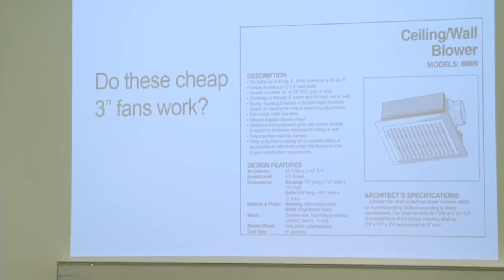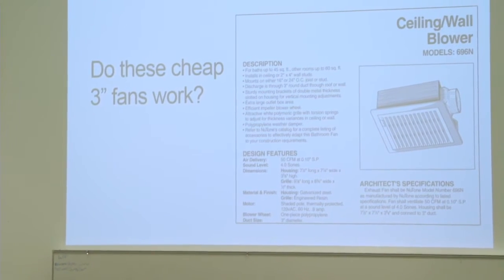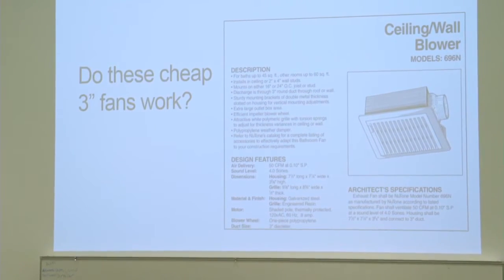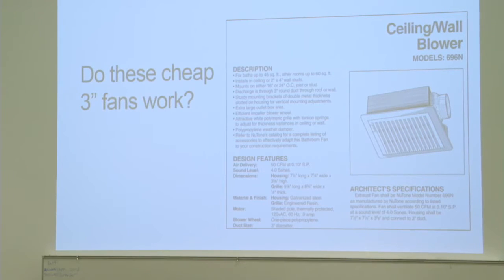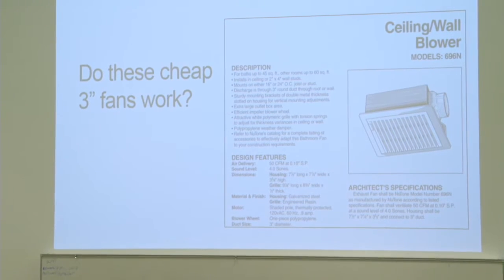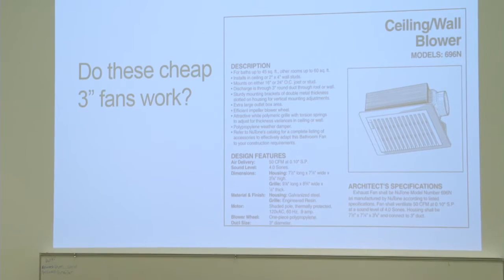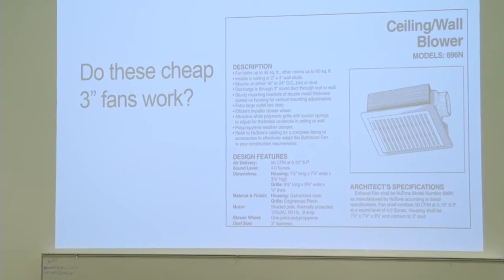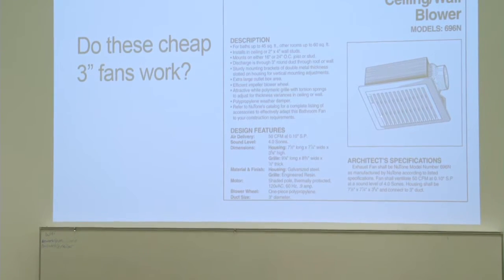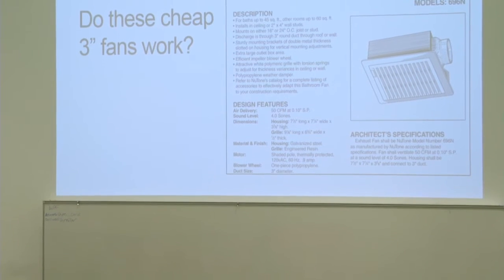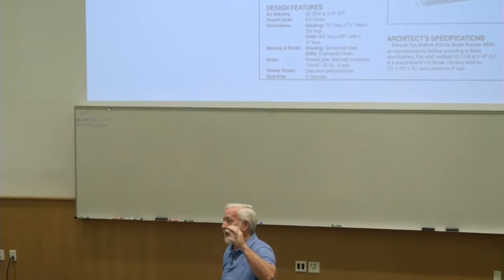And the last thing I wanted to hit on real quick, the code says even if you don't mechanically ventilate, that you have to have a minimum 50 CFM fan for the bathroom, and it actually says you're supposed to have a 100 CFM fan in the kitchen. And we're not enforcing that, but for starters, the bath fan, that cheap fan, does not move 50 CFM when installed, period. No 3-inch fan, and I've searched and searched and searched. I cannot find a 3-inch fan that'll move 50 CFM at 0.25 inches of static pressure, which is the code requirement.